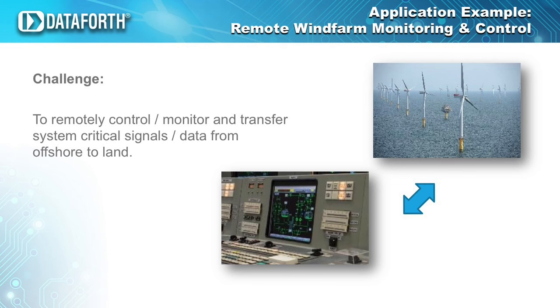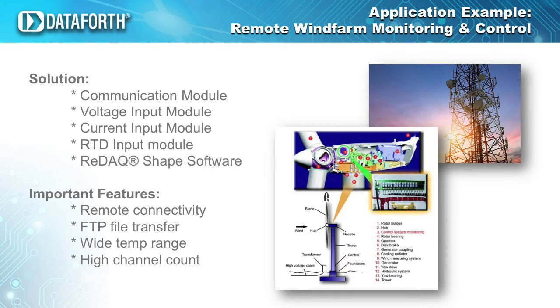Because of the number of wind turbines needing monitoring and control, a low-cost, compact, rugged, and flexible data acquisition solution was desired. Additionally, the most important parameter was remote connectivity. Those requirements posed an interesting design challenge. Indeed, this application is unique because wind turbines operate in many different geographical locations, dictating a wide range of environmental conditions. This includes extremes such as 100% humidity, high vibration, and ambient temperatures from -40 to +85 Celsius.